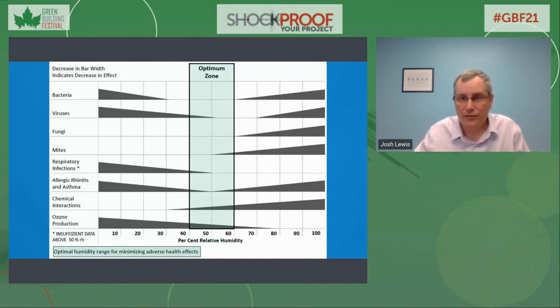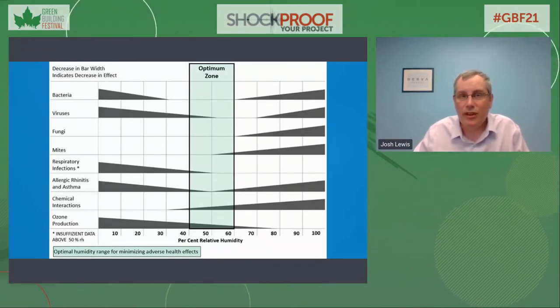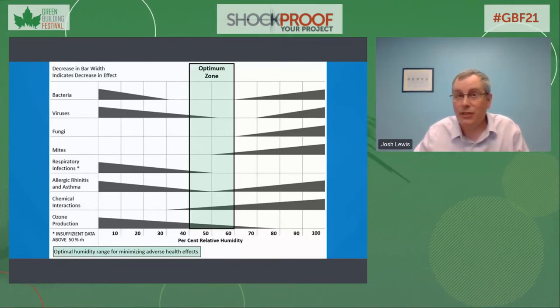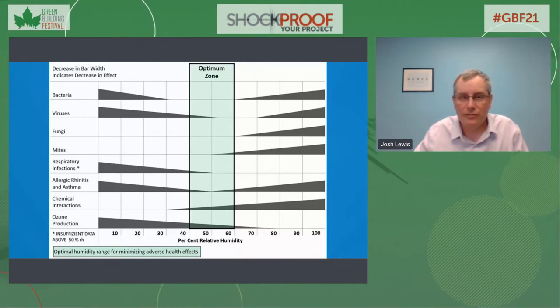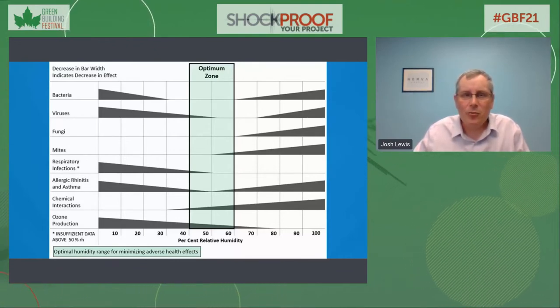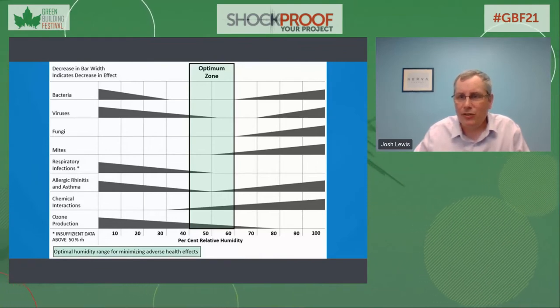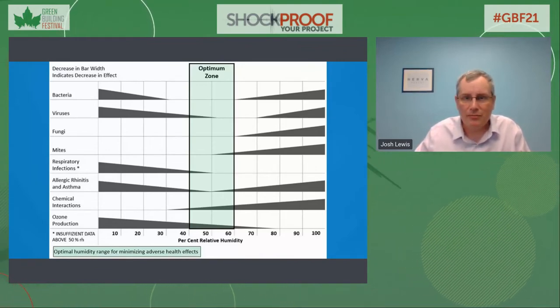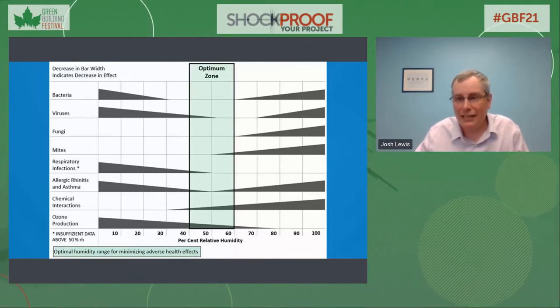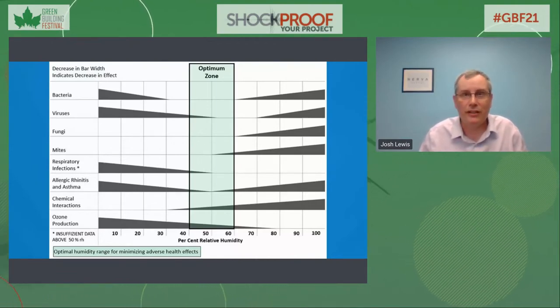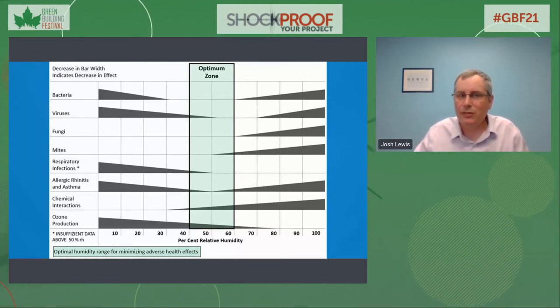In the past, the most common types of buildings to have year-round humidity control, other than healthcare facilities, were those containing Class A or top-tier office space, but typically not other facilities. In our buildings in Canada, we typically do a good job of maintaining indoor humidity levels in the optimum range in the summertime because our air conditioning systems are designed primarily to dehumidify the air, as that is the largest portion of the cooling load which has to be addressed in order for the cooling system to be effective in our climate. But in the winter, the air inside the vast majority of buildings will typically have low humidity levels, usually between 10 to 30%.